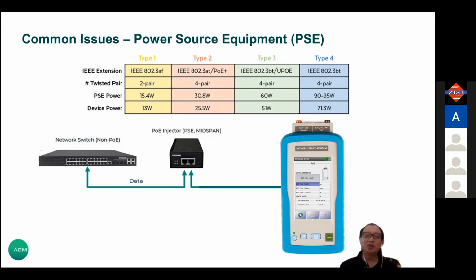Look at the row called device power, which is the minimum output at the end of the cable that you need to power your devices. If you're using 15.4 watts, at the end of the cable you should measure at least 13 watts. If you're using 90-watt power, regardless if it's a 10-meter, 30-meter, or worst case 90-meter cable, the minimum wattage you should receive is 71 watts.